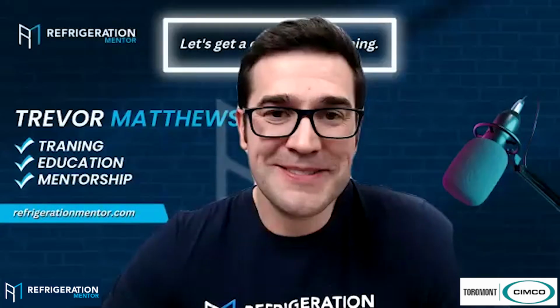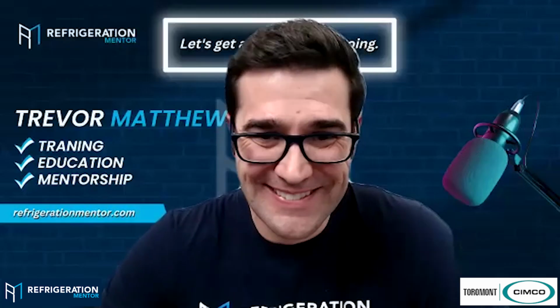Longer in the building. Exactly. Even if the insulation is made, I wouldn't say cheap. I was just about to use that word. But let's say there's an issue with the insulation on the piping, and you do have a failure in the piping. Are you at risk of compromising your steel pipe with rust and eventually failure?